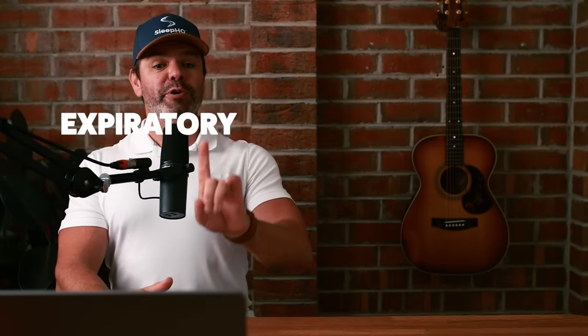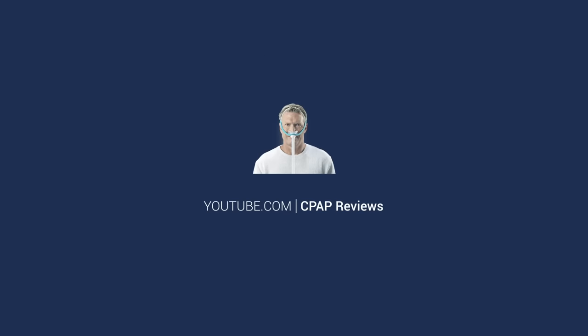G'day mates. ResMed EPR, or expiratory pressure relief, is a powerful therapy setting masquerading as a comfort setting. It was originally developed to make breathing easier by reducing pressure delivery during exhalation. However, what ResMed conveniently fails to mention is it dramatically reduces apnea control, unlike pressure relief technology found on some other devices.